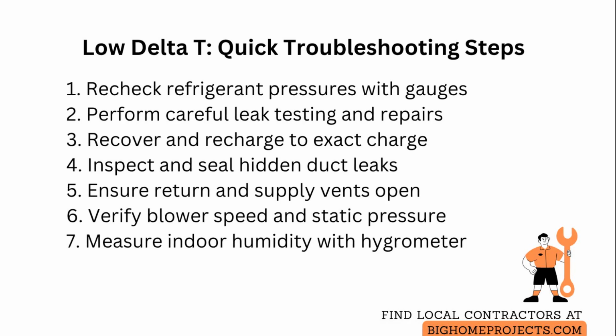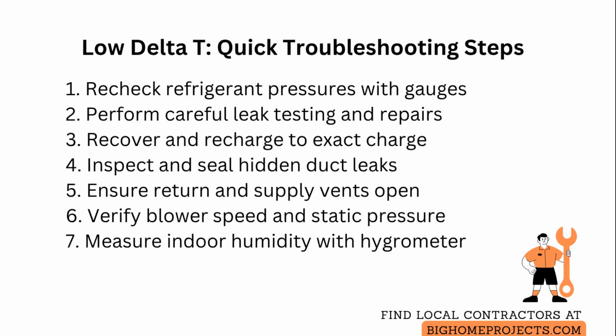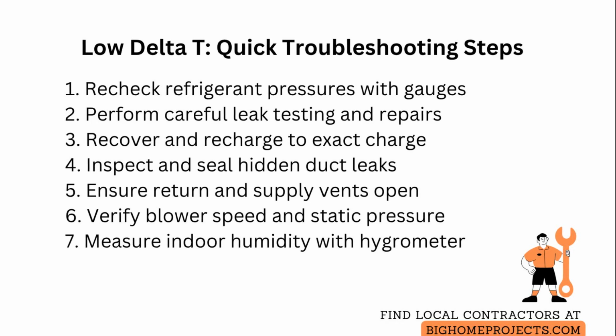Finally, confirm the coil is not bypassing air through a misaligned damper or short circuit in the duct layout, and check for a frozen or partially iced coil, which indicates either insufficient airflow or a refrigerant issue.